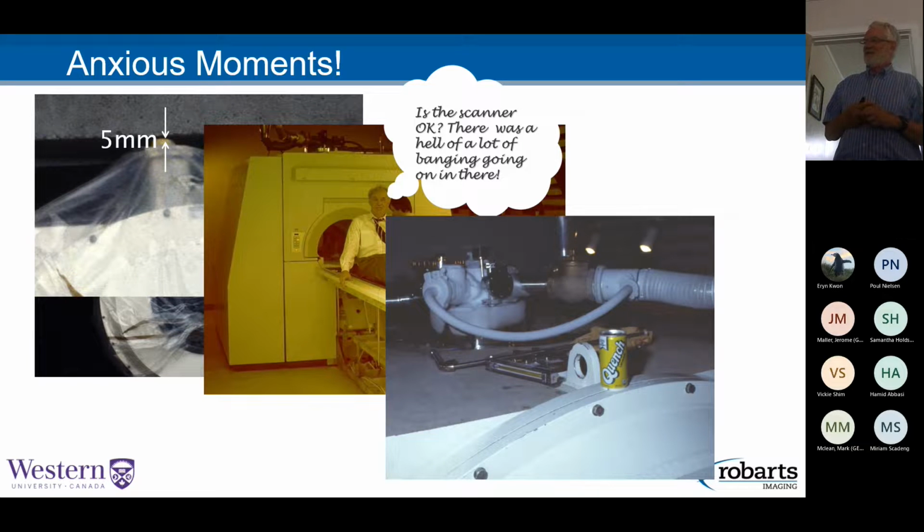We had a quench for ours. Yeah, Wessel's being ramped up. Yeah, our 70 in London quenched about September. It's not back up in field yet. Oh, okay. Well, I think it got up to field yesterday, but they're going to take another 3 weeks to shim it and test it. Yeah, nasty problem when the magnet loses its superconducting. Yeah.